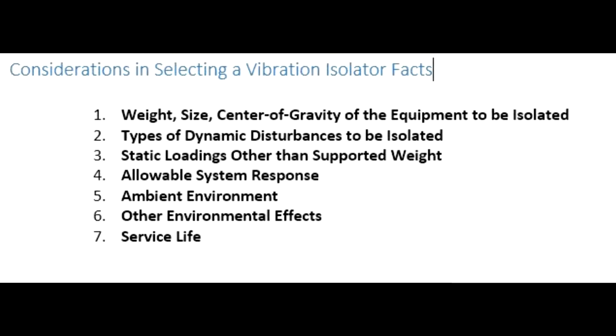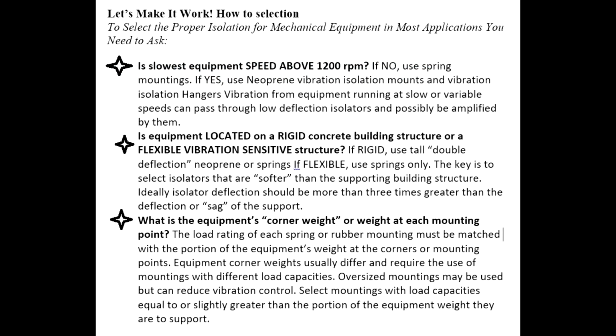There are some factors to consider in selecting a vibration isolator: weight, size, and center of gravity of the equipment to be isolated; type of dynamic disturbance to be isolated; static loading other than supported weight; allowable system response; ambient environment; other environmental effects; and service life. Let's make it work. How to select.